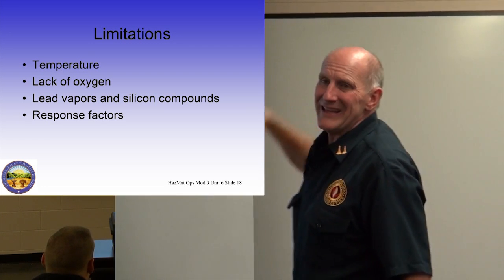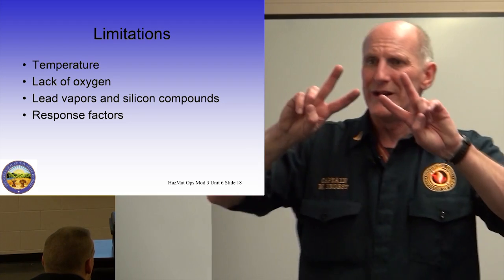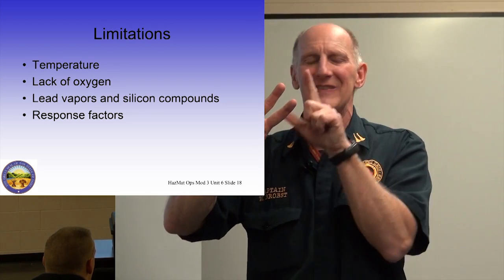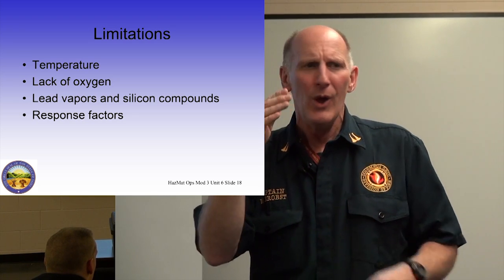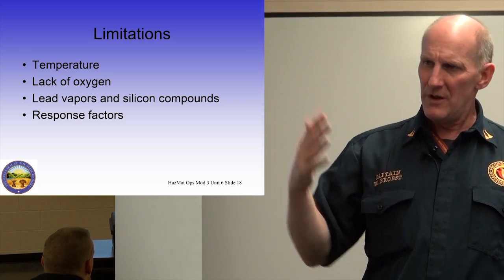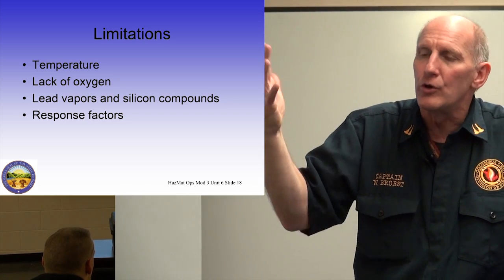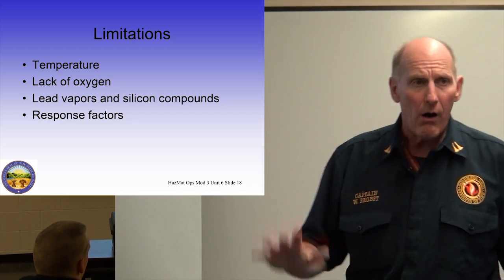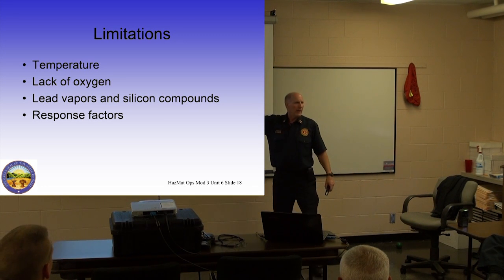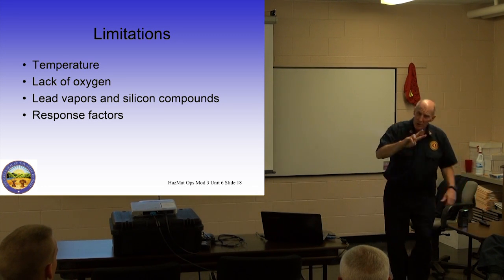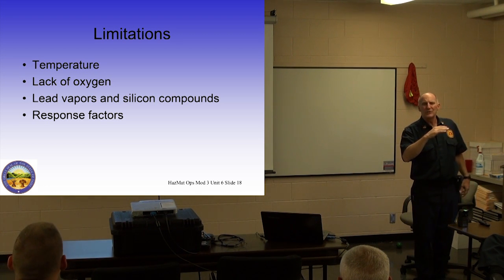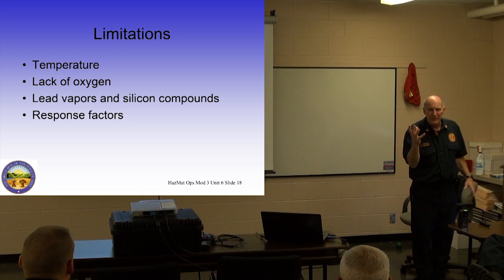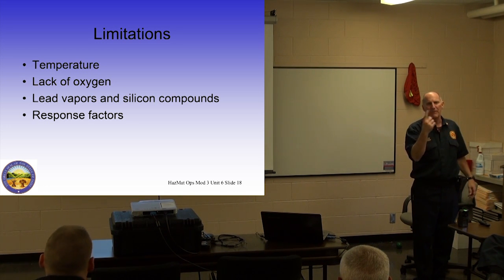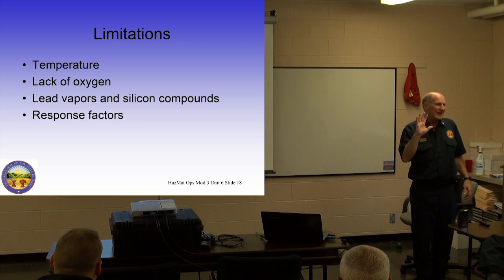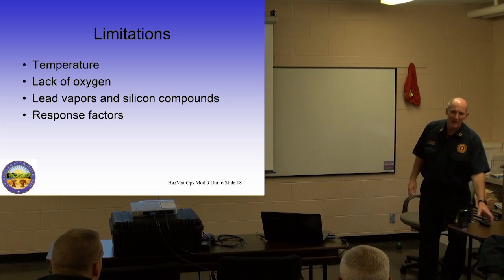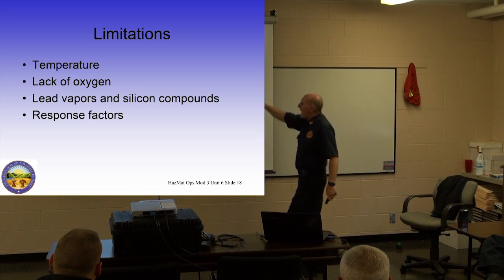But the problem with the LEL sensor is, if I walk into an atmosphere that doesn't have enough oxygen in it, this sensor will burn dimmer, which will give you negative numbers. Well, there's no such thing as a negative 2 part per million or 2% of something flammable in the air. All it's telling you is the oxygen's screwed up. And if at the same time that the oxygen is a little bit deficient and the LEL is back up a little bit, if I'm at a -2 because of oxygen and a +2 because of the flammable, it's reading 0 on your meter and you're going to think it's safe. It is not safe.